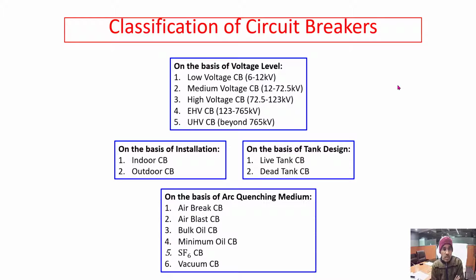Next, on the basis of installation: indoor circuit breaker and outdoor circuit breaker. This is where the circuit breaker is installed. And then another way, on the basis of tank design. Tank design is also an important consideration in circuit breakers. Therefore, there are two types here: live tank circuit breaker and dead tank circuit breaker.